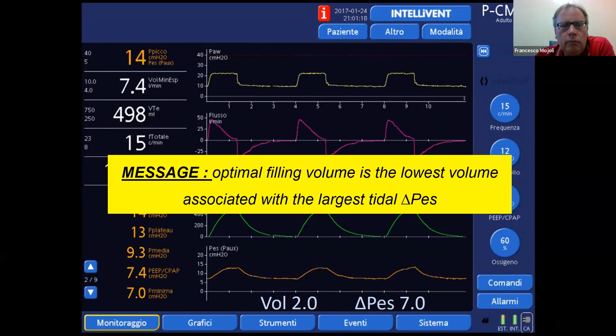At this time, you are almost ready for the validation test. I suggest just checking 2 other things. One is the shape of your esophageal pressure curve. This should be as similar as possible to that of the volume. And if you have the possibility to select an esophageal pressure volume loop, like you see on the right of the slide, this should be aligned, so no hysteresis. And actually, the slope of this line is the compliance of the chest wall.